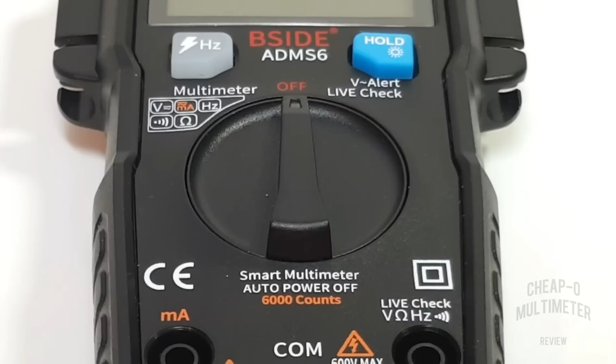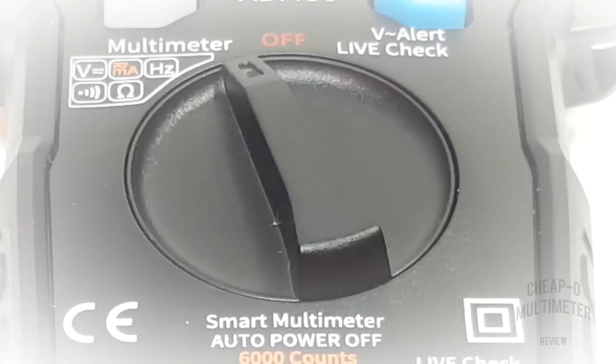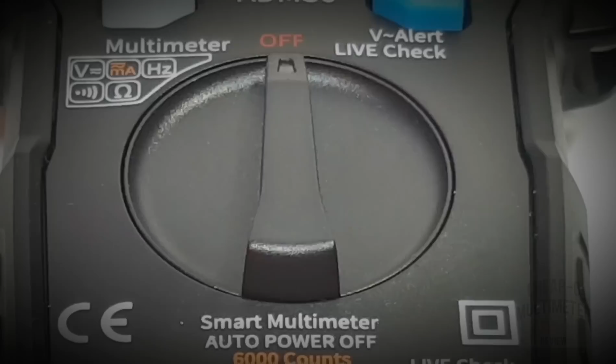Turning the meter to the right, you are in voltage alert, also known as live check mode. Turning it to the left, you are in multimeter mode, where you have your functional feature set: volts AC/DC, milliamps, frequency, continuity, and resistance. That is it. 12 o'clock is the off, the one and only off position.